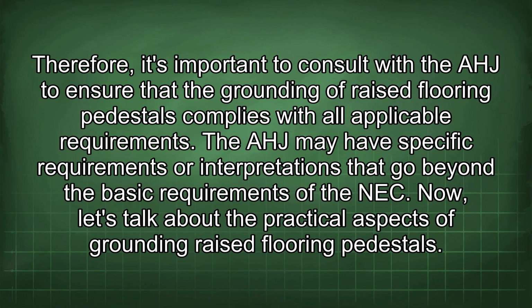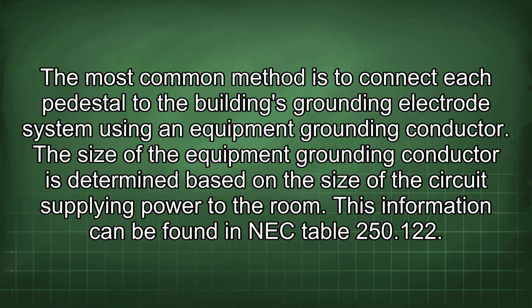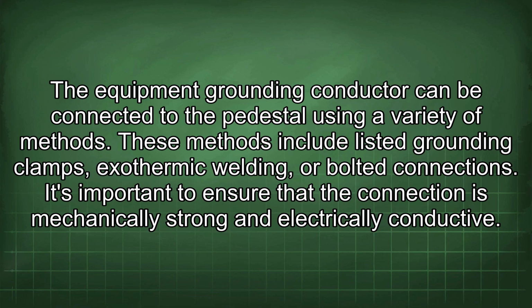Now let's talk about the practical aspects of grounding raised flooring pedestals. The most common method is to connect each pedestal to the building's grounding electrode system using an equipment grounding conductor. The size of the equipment grounding conductor is determined based on the size of the circuit supplying power to the room. This information can be found in NEC Table 250.122. The equipment grounding conductor can be connected to the pedestal using a variety of methods. These methods include listed grounding clamps, exothermic welding, or bolted connections. It's important to ensure that the connection is mechanically strong and electrically conductive.